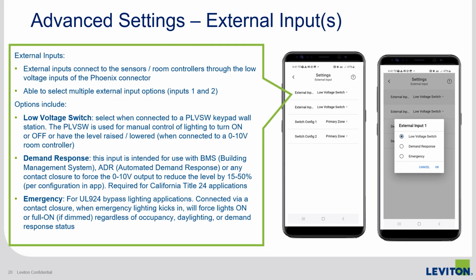External inputs is the next section we'll cover in advanced settings. These are the low voltage inputs where you may have connections to the sensor using the Phoenix connectors. These low voltage connections are used for the following inputs. Low voltage switch. Select this option when connecting to a PLVSW keypad wall station. These are used to provide manual or on-off control when connected to a switching-only sensor, or dimming versions when connected to a 0 to 10 volt dimming room controller.